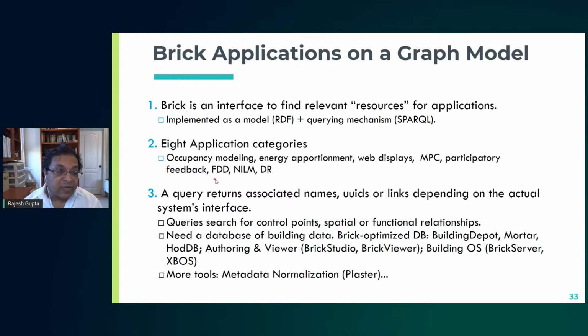FDD refers to fault detection and diagnosis, and this basically means identifying if there are faults in the system. It could be under normal conditions, for example, some part of the HVAC system is degraded, or it could be under extraordinary conditions like the building needs to be evacuated: which room is occupied, which room is not occupied. NILM refers to non-intrusive load monitoring. So here, monitoring without actually having equipment monitoring, that is, inferring the load based on other information. And demand response, or DR, which is the ability to control usage.